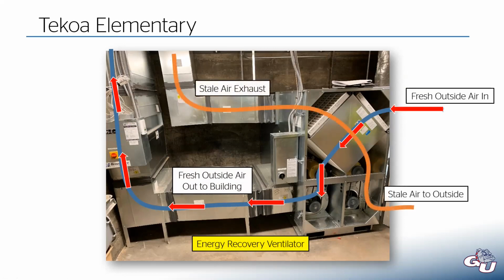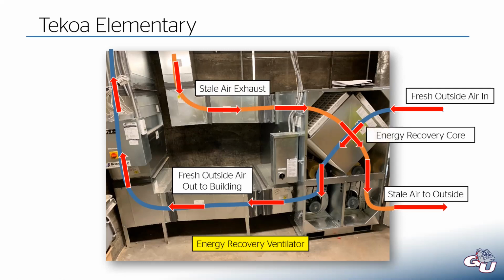But then I mentioned we also need to get rid of the stale air. And so this is pulling air out of the building that's, you could say, used. It's already served its purpose. It's already ventilated the space and people have breathed it in and breathed it out. So that's going to be our stale air coming out. And you can see those two air paths actually cross in what's called the energy recovery core. I'll talk about that more in a second. On the bottom here, it's kind of hard to tell, but there are two fans. And those fans are what's moving the air in each of those paths.